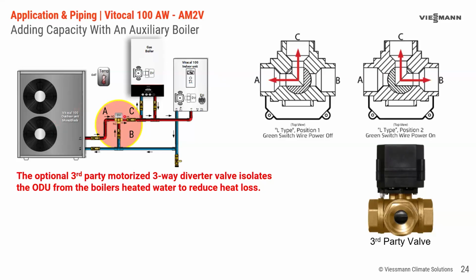So we might want to put this electric bypass valve in here, and it would be a powered open spring return type valve because we're only going to power it one direction. Basically, we're going to power it closed, and when it's not being closed, we're going to let the spring return it open. And what I mean by closed is closing the path through here. We're going to bypass it so the water goes around like this, right?